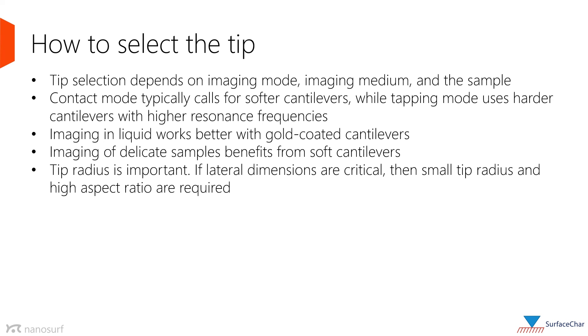Tip selection is critical for good images. The tip has to be tailored to imaging mode, imaging medium, and the sample. Contact mode typically calls for softer cantilevers, while tapping mode uses harder cantilevers with higher resonance frequencies. Imaging in liquid works better with gold-coated cantilevers, since gold is more inert and better at preserving its reflectivity in solution. Delicate samples require softer cantilevers. If lateral dimensions of features are critical, then a small tip radius and high tip aspect ratio are required.